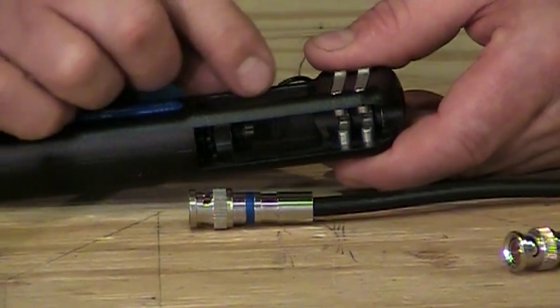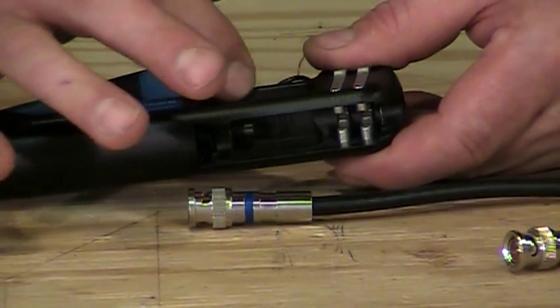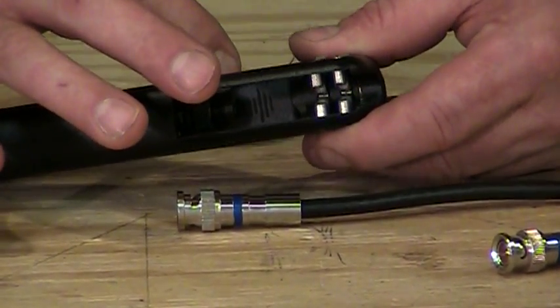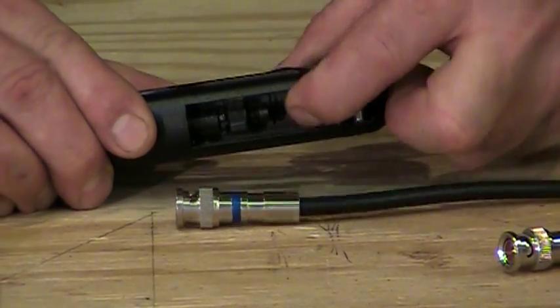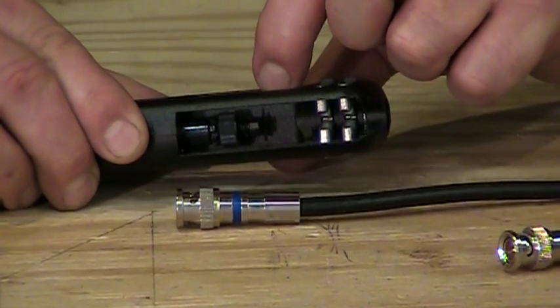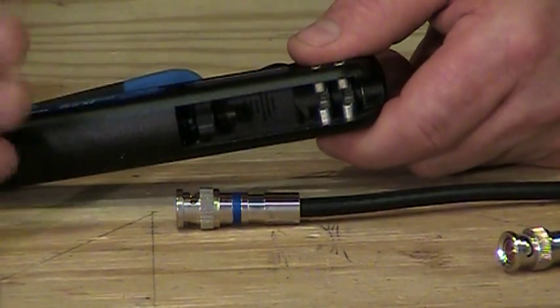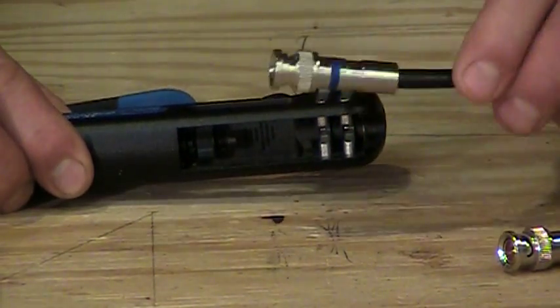And again, with the Ideal product line, you'll see that there's little gradients, little markings inside the tool there. And the large marking, when I move the ram all the way forward, it should be even with that largest marking you see inside here. And then I know that's ready for any of Ideal's connectors.